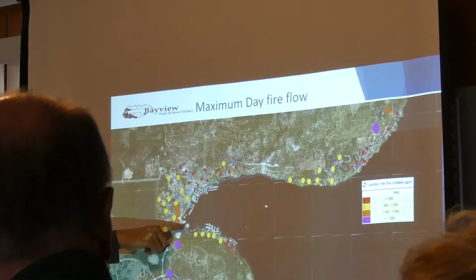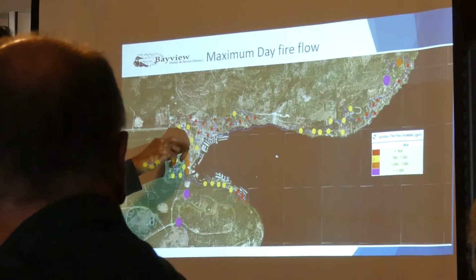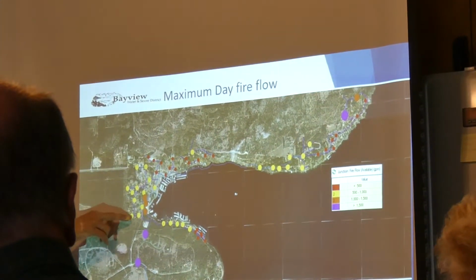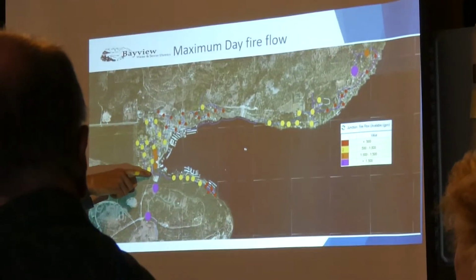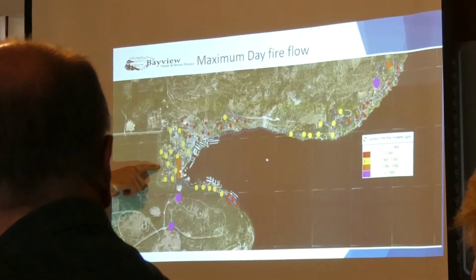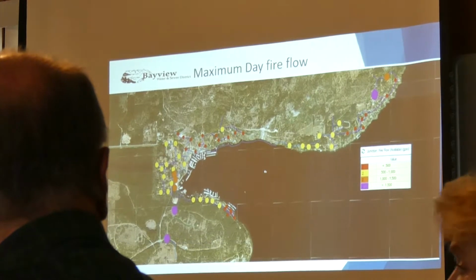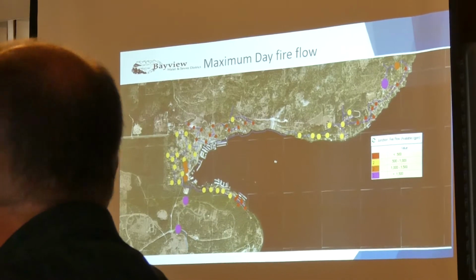So you've got pressure reducing to lower the pressure. So if you ran that line around this way, then you'd bring that high pressure up here, and we'd put pressure reducing valves here and here to lower pressure going back down. So your question was, could you keep the existing system? And essentially what you have is just small pipes. You've got a 12-inch that goes here, but mostly 4s and 6s in this area. And so there's just not very much capacity. You just can't get much water through them. So that 12-inch coming around like this gives you a lot better ability to feed that area. That's a great question. Does that make sense to everybody? I'm glad you stopped me.